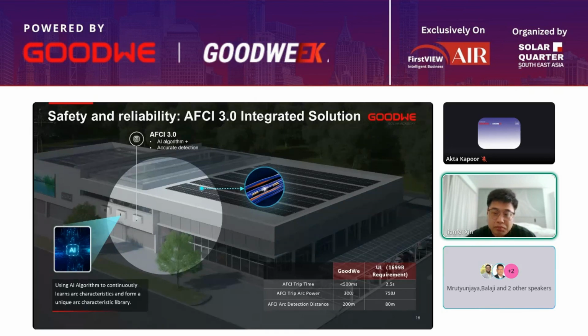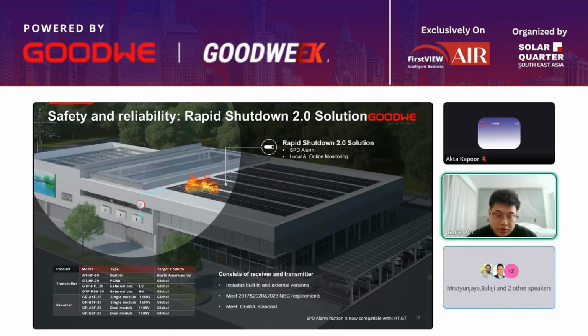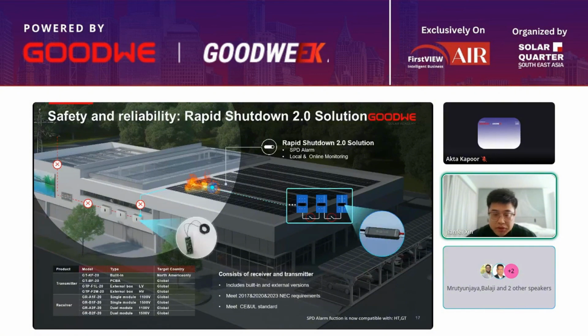So we can guarantee to protect against fire risk by switching off or working off the inverters, and also offer alarms to our inverters and platform for customers, along with the RSD rapid shutdown for emergency situations. RSD means we can use automatic or manual switches to cut down all of the panel connections. This method is mainly focused on protecting firefighters.